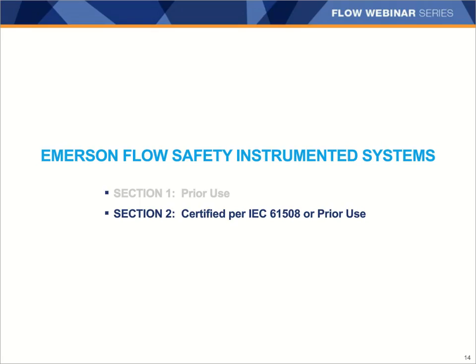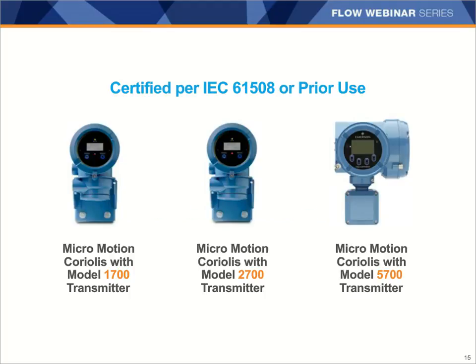So we've talked a lot about our prior use products. Let's now talk about some of the Emerson instruments for flow that are certified devices per IEC 61508. Emerson offers Micro Motion Coriolis meters with the model 1700, 2700, or 5700 transmitter for use in safety instrumented systems. These devices are all available as certified devices per IEC 61508, and they can also be used as prior use devices. The prior use designation is applicable to the 1700 and 2700 devices. They're all certified as SIL 3 capable, and we also have additional products that have been used as prior use devices too that I don't have listed here.